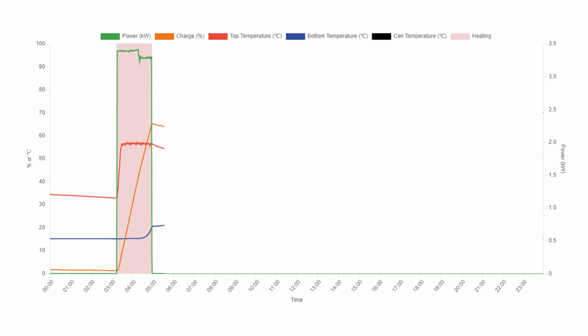At this point, the tank will begin operating its destratification pump to ensure the water is heated downwards. Once the hot water reaches the bottom of the tank, you'll see the blue line jump slightly. The bottom 35% of the tank won't really be heated, but some of that heat would have leached down to the bottom.